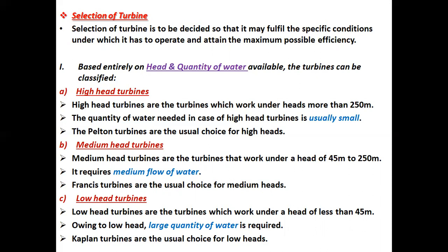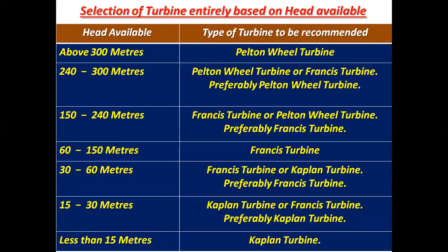C, low head turbines. Low head turbines are the turbines which work under a head of less than 45 meters. Owing to low head, a large quantity of water is required. Kaplan turbines are the usual choice for low heads. Selection of turbine entirely based on head available. Above 300 meters, type of turbine to be recommended: Pelton wheel turbine. 240 to 300 meters, Pelton wheel turbine or Francis turbine, preferably Pelton wheel turbine.